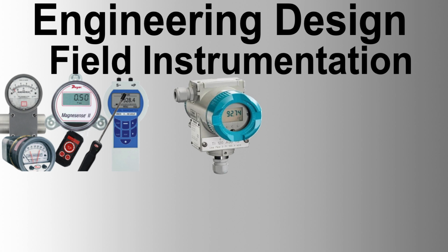Thermowells must be designed to withstand hydrostatic testing conditions and must have wake frequency and stress calculations provided in accordance with ASME PTC 19.3. The thermowell immersion length must place the measuring element in the middle third of the pipe. Shorter immersion lengths may be accepted, where wake frequency and stress calculations limit the immersion length provided the required accuracy can still be achieved. Where thermowells are required in line sizes smaller than 4-inch NB, the thermowell line must be swaged up. Test wells must have a screwed plug and chain.